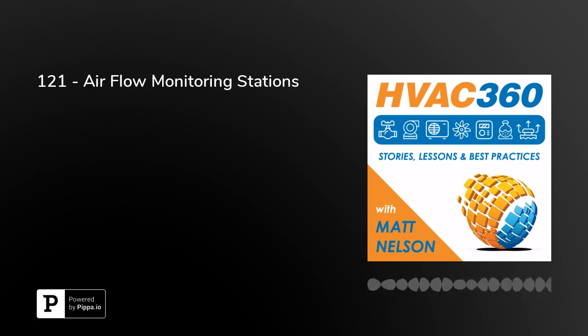Depending on the size of the duct, you might have one of these tubes put in the side of the duct. Sometimes you're going to have 2 or 3, and that all depends on the number of points that you want to gather and the average. So size of the duct, all that matters. Other form factors that you can do, the small rooftop units or ERV units, they also have some sort of device that you can install in the inlet that will measure the airflow. And again, we're measuring velocity here over an area, so that's how we get the CFM.